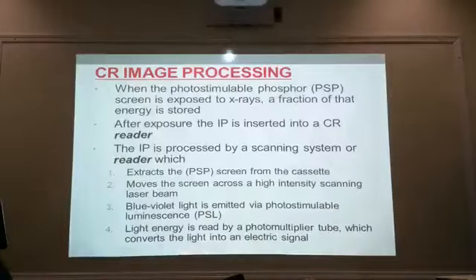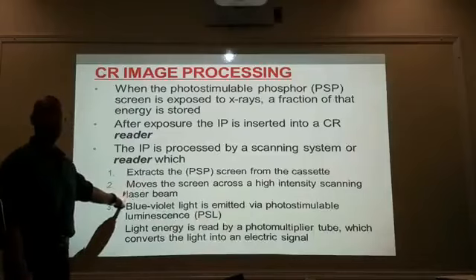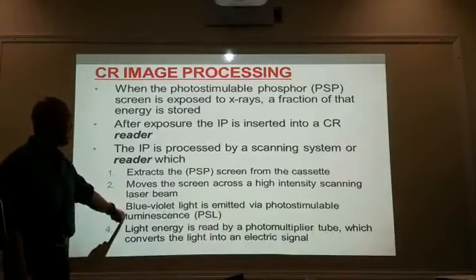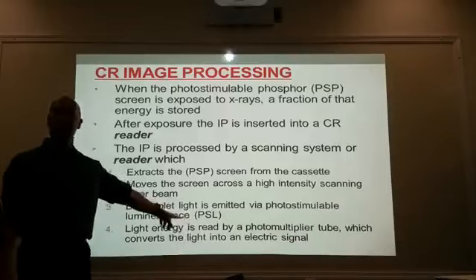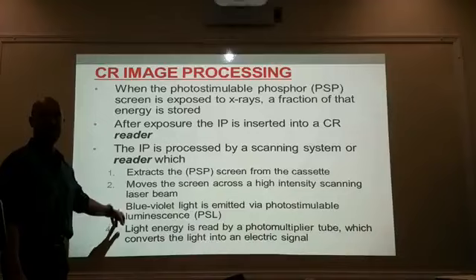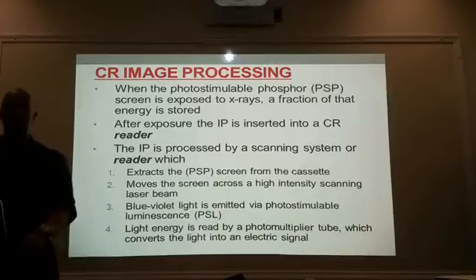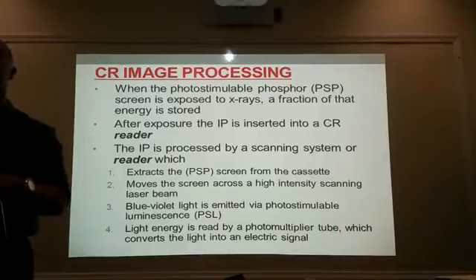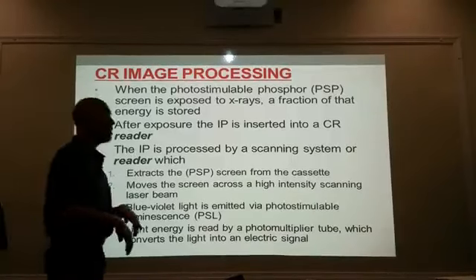As it's being scanned, the crystals are going to emit a blue-violet light. The screen is removed, scanned by the laser beam, and the crystals then start to emit a blue-violet light. This is the characteristic PSL — photostimulable luminescence — releasing the blue-violet light. Now this light energy is an analog signal.